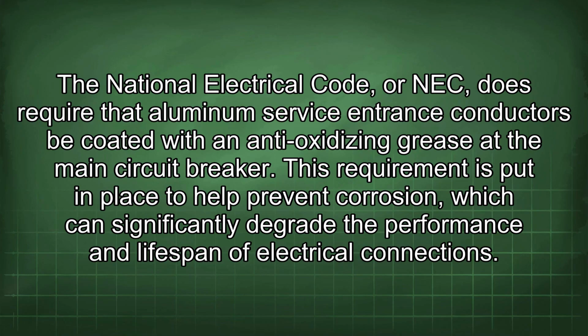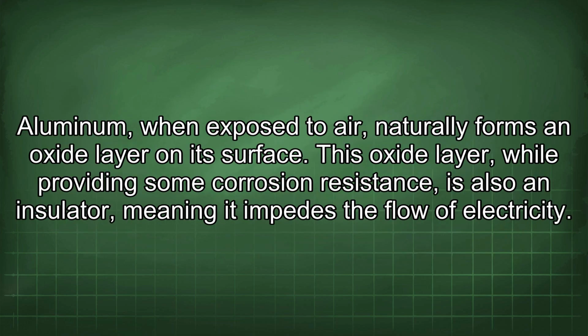The National Electrical Code, or NEC, does require that aluminum service entrance conductors be coated with an anti-oxidizing grease at the main circuit breaker. This requirement is put in place to help prevent corrosion, which can significantly degrade the performance and lifespan of electrical connections. Aluminum, when exposed to air, naturally forms an oxide layer on its surface. This oxide layer, while providing some corrosion resistance, is also an insulator, meaning it impedes the flow of electricity.